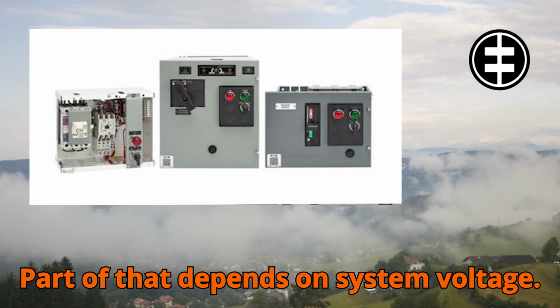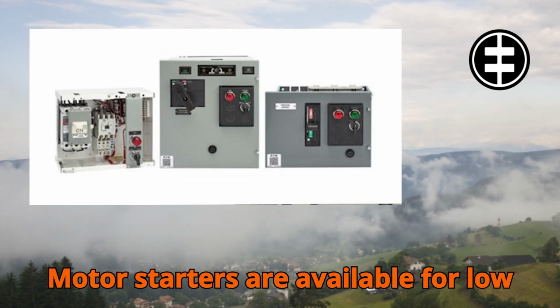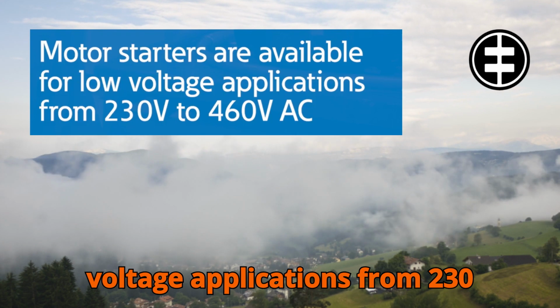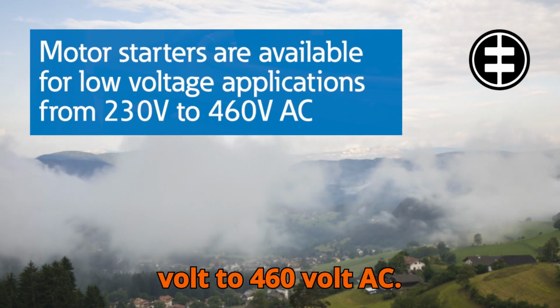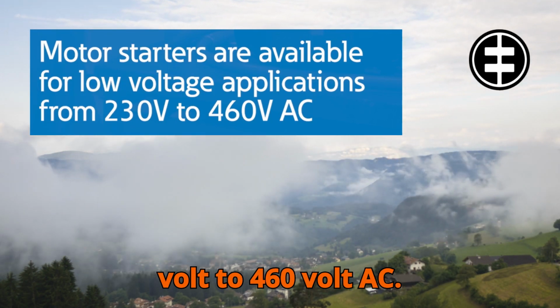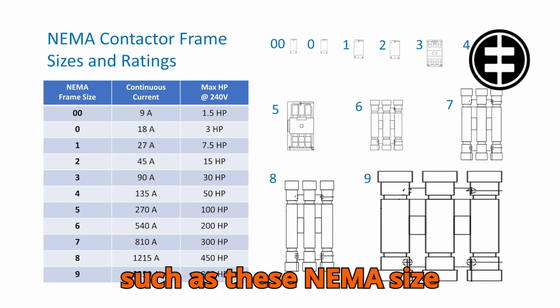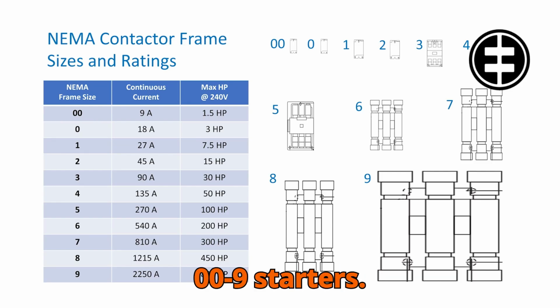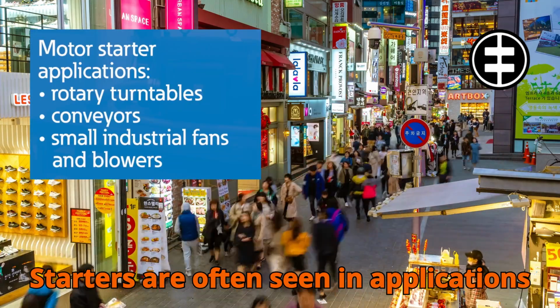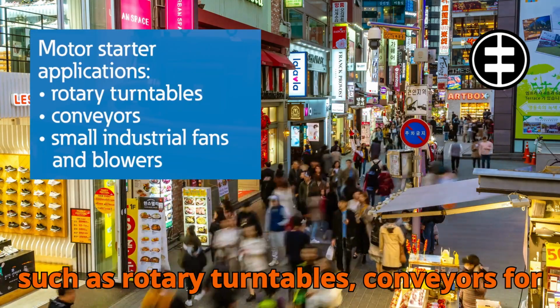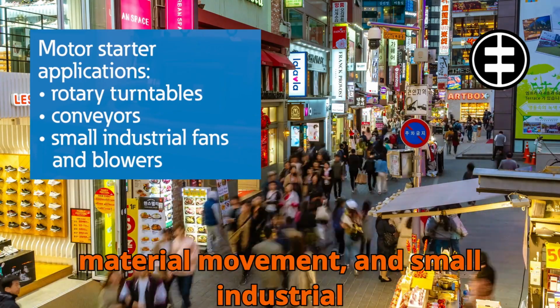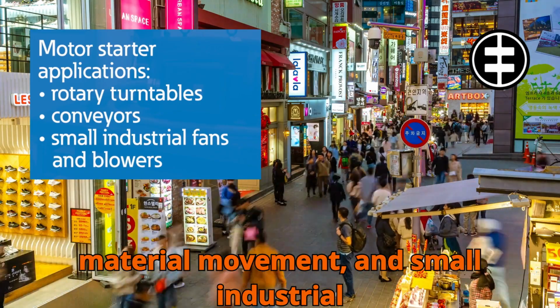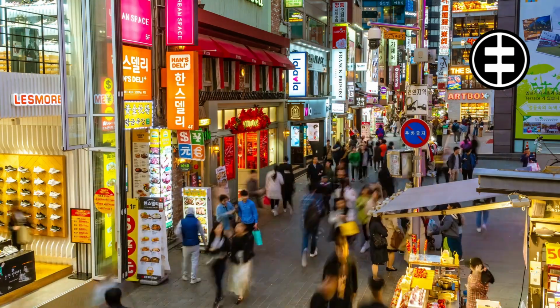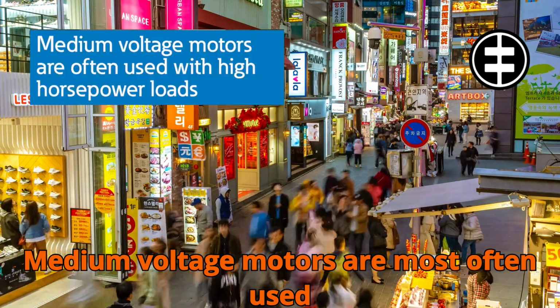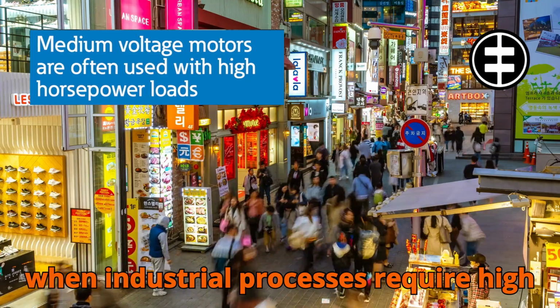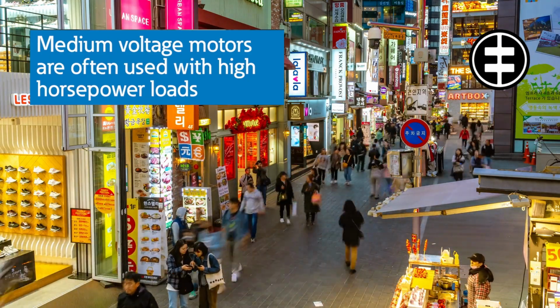Part of that depends on system voltage. Motor starters are available for low-voltage applications from 230 volt to 460 volt AC, such as these NEMA-sized 00 through 9 starters. Starters are often seen in applications such as rotary turntables, conveyors for material movement, and small industrial fans and blowers. Medium voltage motors are most often used when industrial processes require high horsepower loads.